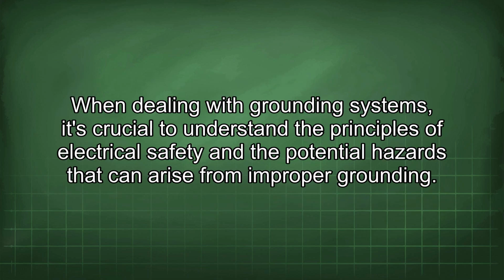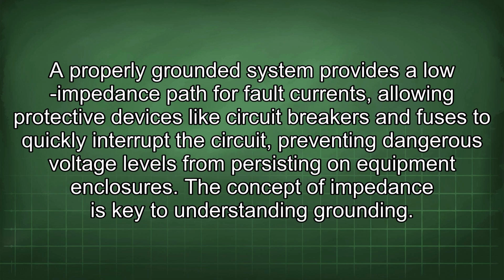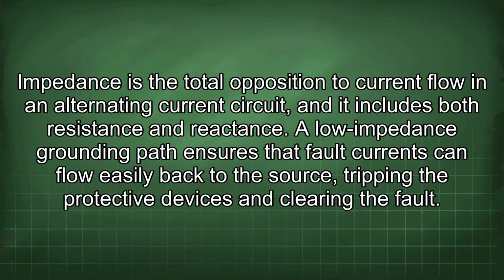When dealing with grounding systems, it's crucial to understand the principles of electrical safety and the potential hazards that can arise from improper grounding. A properly grounded system provides a low impedance path for fault currents, allowing protective devices like circuit breakers and fuses to quickly interrupt the circuit, preventing dangerous voltage levels from persisting on equipment enclosures. The concept of impedance is key to understanding grounding. Impedance is the total opposition to current flow in an alternating current circuit, and it includes both resistance and reactance.